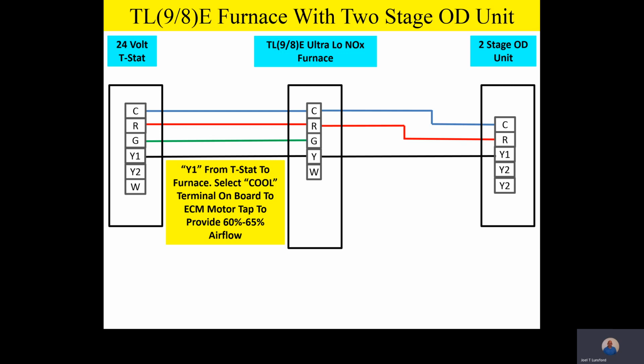So Y1 call from the thermostat, Y call on the furnace to Y1 outside is our first stage cooling call on a 2-stage product. And the capacity of that 2-stage product on a Y1 call is about 67% capacity. That's why we want to have our airflow inside matching that as close as we can. So be sure and select the motor speed tap to provide 60 to 65% airflow on a Y1 call.